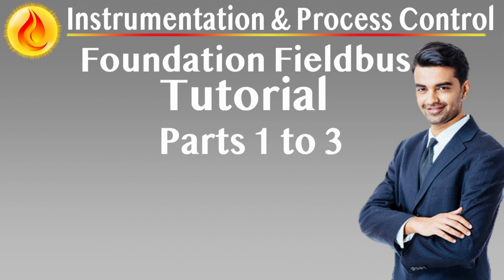Unlike conventional 4-20 milliamp systems, Fieldbus enables multiple devices to operate on a single segment, reducing cabling, simplifying architecture, and enhancing diagnostic capabilities. One of the most prominent features of Foundation Fieldbus is its ability to allow multiple field devices, such as transmitters, actuators, and controllers, to communicate simultaneously on the same bus. Each device can transmit and receive messages using deterministic scheduled communication protocols.